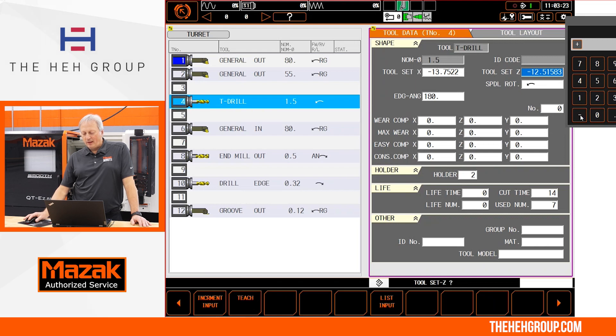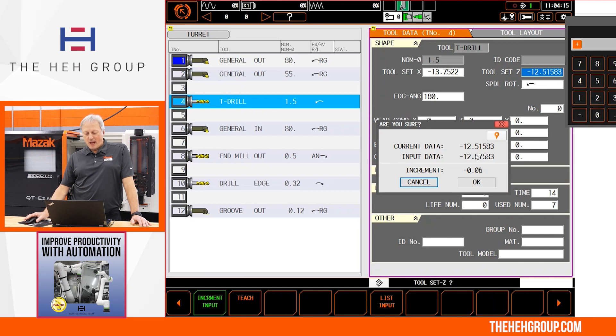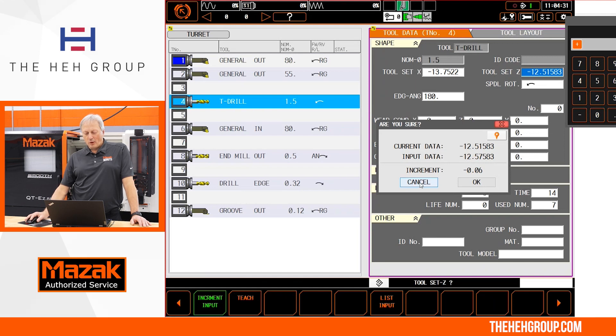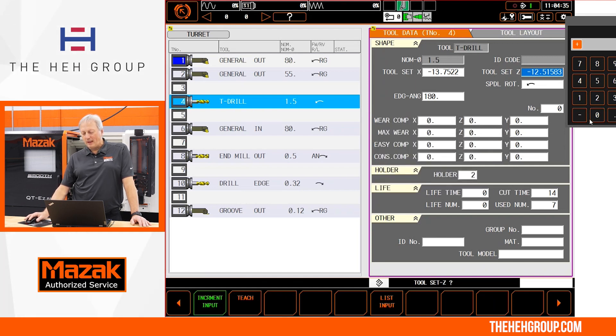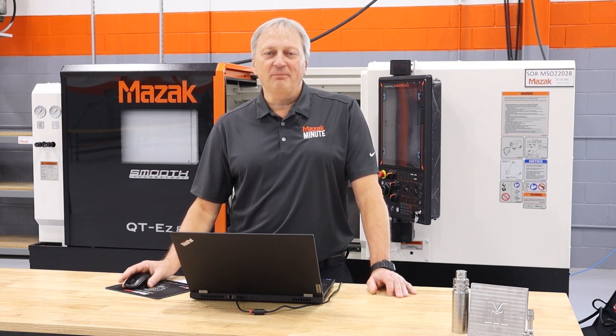Now let's repeat it with a different error. I'll highlight the increment soft key and increment the value by 60 thousandths. Pressing input shows the current data, the inputted data, and the increment of 60 thousandths. Since the F124 parameter was set to a maximum of 50 thousandths, this causes an alarm. Hitting cancel, if I adjust by 20 thousandths instead, you will not get the prevention window — it will accept the value and allow the machine to continue. By following these simple steps, you can avoid making a bad part. Thanks for watching, see you next time on the Mazak Minute.